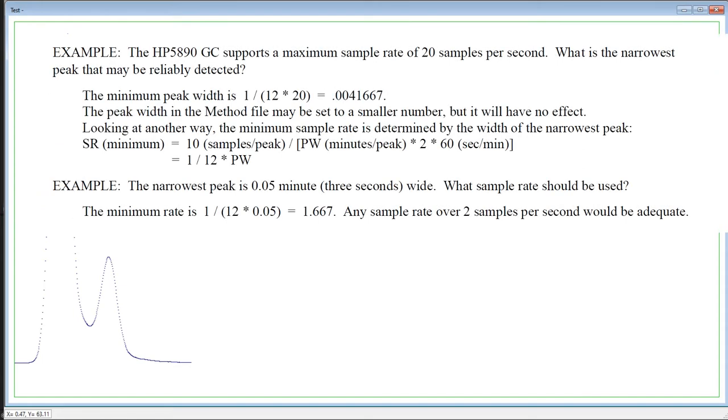Example: the HP 5890GC supports a maximum sample rate of 20 samples per second. What is the narrowest peak that may be reliably detected? The minimum peak width is 1 divided by 12 multiplied by 20 equals 0.0041667. The peak width in the method file may be set to a smaller number, but it will have no effect.